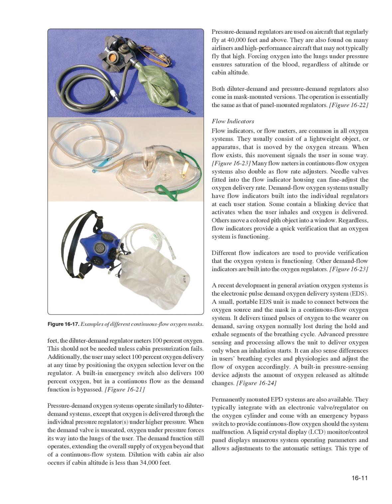Advanced pressure sensing and processing allows the unit to deliver oxygen only when an inhalation starts. It can also sense differences in users' breathing cycles and physiologies, and adjust the flow of oxygen accordingly. A built-in pressure sensing device adjusts the amount of oxygen released as altitude changes.